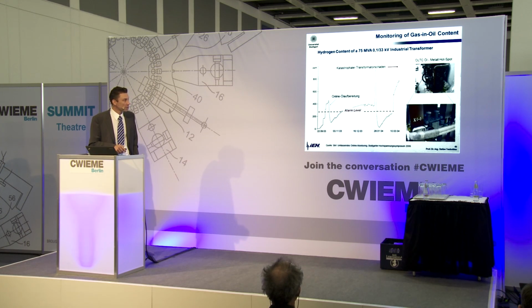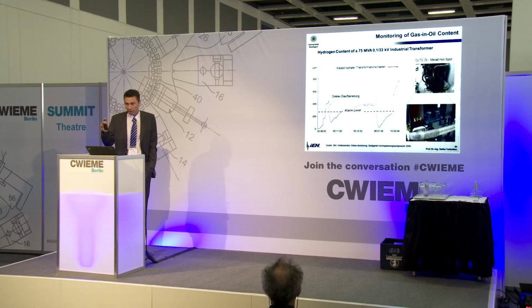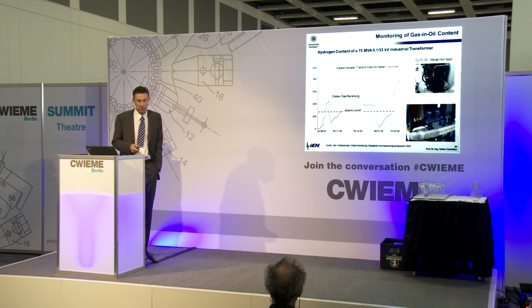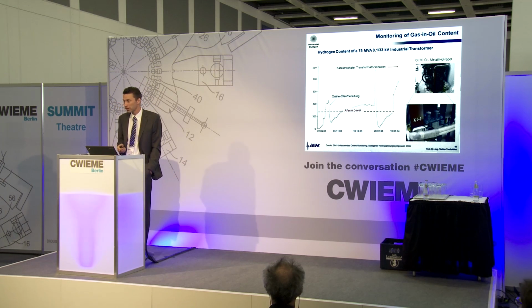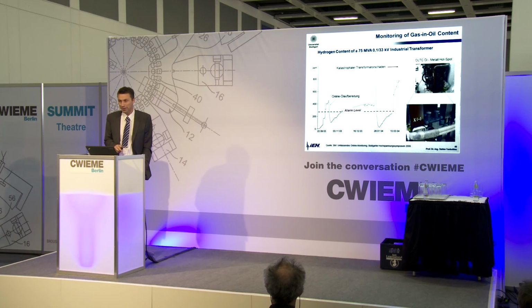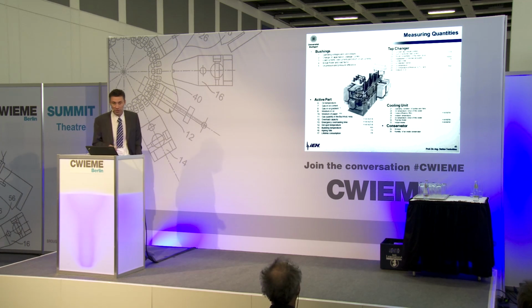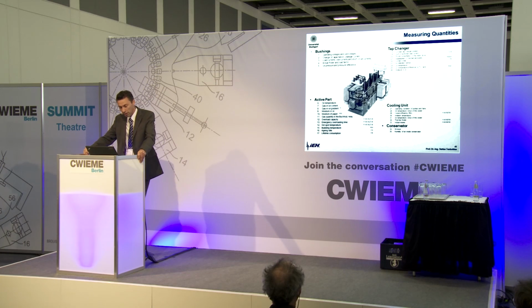The reason was, at this point we gave an alarm, so we sent a fax message to the utility and said you have to do something, but this was on Friday at lunchtime. And you know what is happening with a fax which you receive Friday at lunchtime. This should have time to wait until Monday. But unfortunately on Saturday the transformer said, no, it's now a good time for me to pass away. So if you install such a monitoring system, you also have to believe and react to the indications of the system.